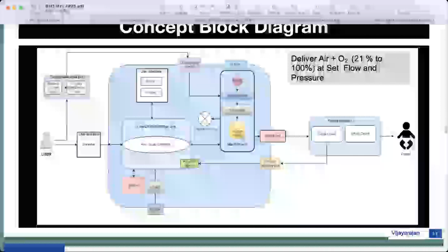You can't just put in oxygen and air and expect a certain percentage of oxygen. It has to be managed at the right level. And when you add this, the output pressure will vary, and flow will vary. So I have to manage these three parameters as outputs, by managing the oxygen input and this blower input, where the normal air comes in. I have only two things to adjust: how much oxygen I put in and how much air I have. Generally the pressure of oxygen is fixed in the hospital, and sometimes we put in a pressure regulator, depending on the design, so that people can reduce the pressure so it mixes with the air. The air comes with a certain pressure. Both should be at a similar pressure level so that they can mix. So we need to understand some of that physics.